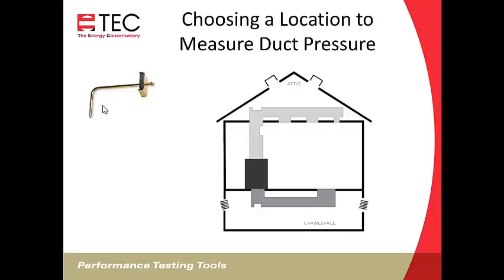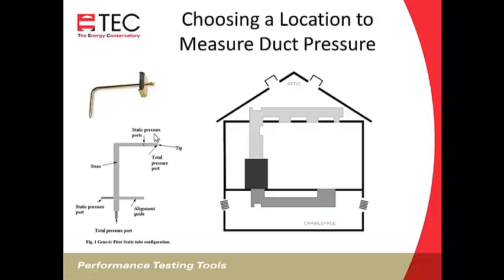And you can think of static pressure as like the bursting pressure in the duct, like you'd be measuring pressure on a balloon or a tire. There's no air movement. You're just measuring the outward pressure of the air in that. So that's what a static pressure probe does. Oftentimes we'll have people calling, they want a new static pressure probe, and they'll refer to it as a pitot tube. A pitot tube is something different. Sometimes those terms are used interchangeably, but you should get in the habit of calling this a static pressure probe and not a pitot tube.